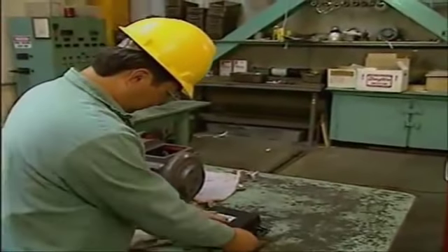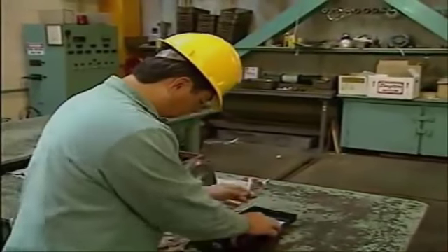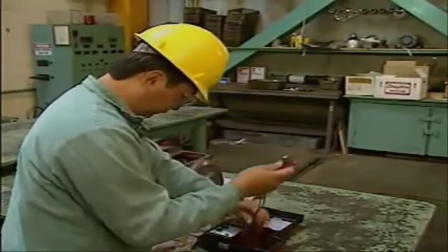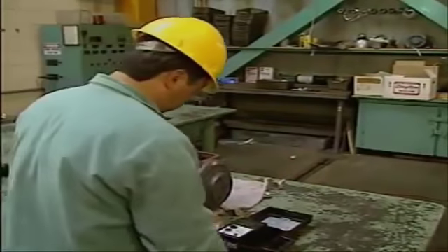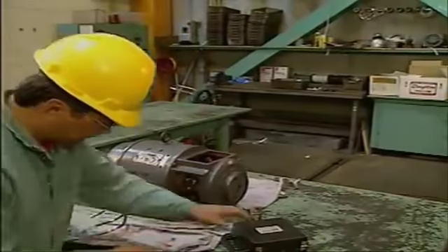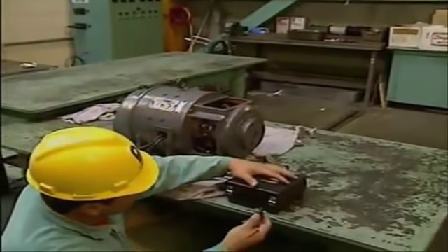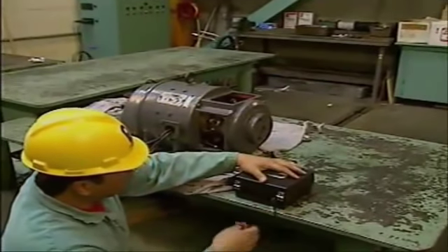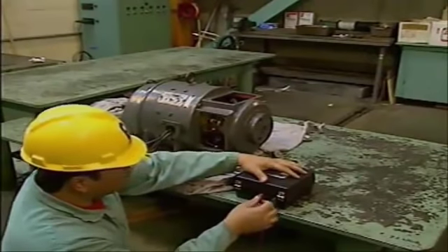A ground is a breakdown in insulation that provides a current path to ground where there should not be a path. An instrument commonly used to check for grounds is a meg-ohm meter. Meg-ohm meters are available in several designs. Some are powered by a hand-crank generator, others are line-powered, and others are battery-powered. The one used in our example is battery-powered.